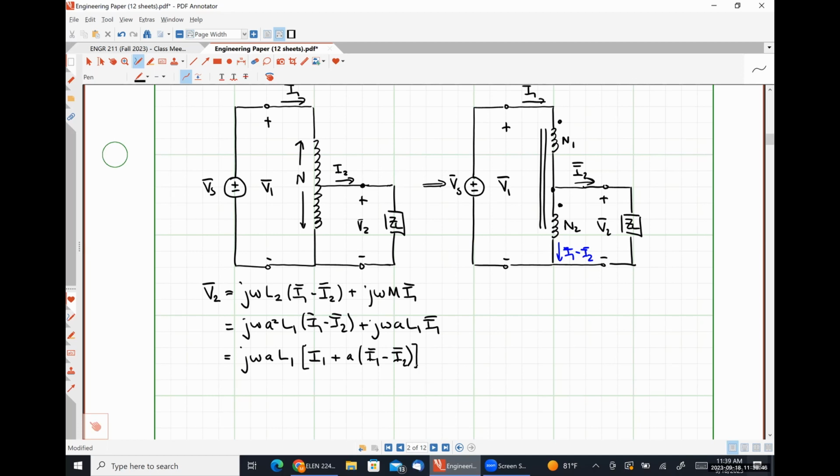That being said, they do not provide electrical isolation between the primary and the secondary. So autotransformers are used a lot in power applications, like in a substation, where you're stepping down the voltage from really, really high levels to a medium voltage, where you don't necessarily need electrical isolation, but you're trying to drop the voltage by a significant amount.